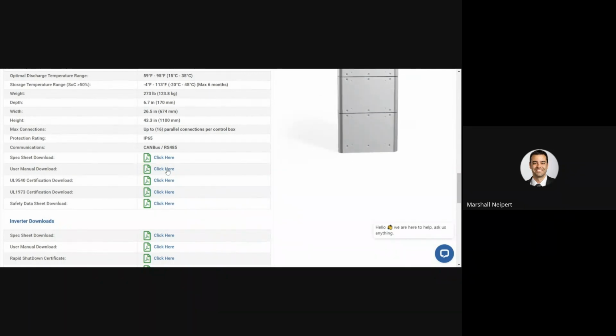On the battery side, you select the menu, go down to the inverter type. It communicates with about 18 different inverter brands through closed loop communication—for example Sol-Ark, the new Solus 48 volt, SMA, EG4, and others listed in the manual.